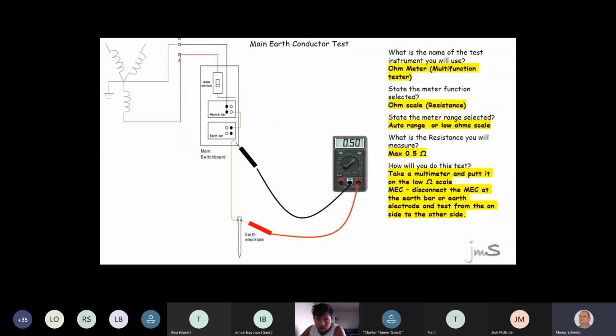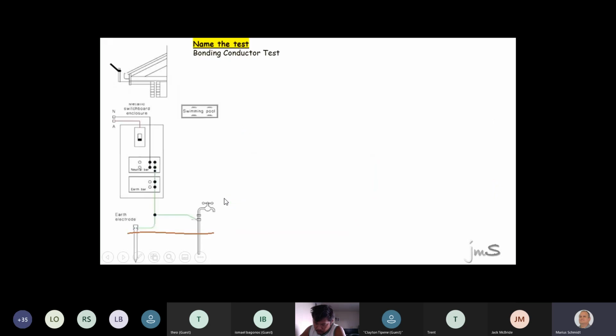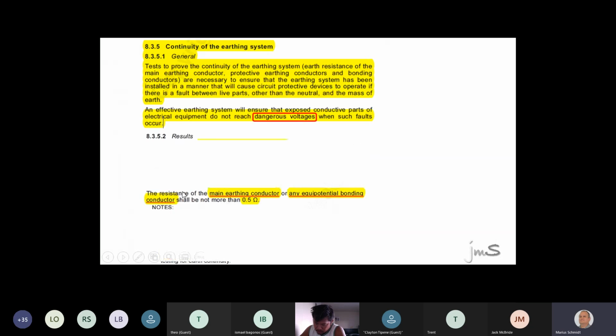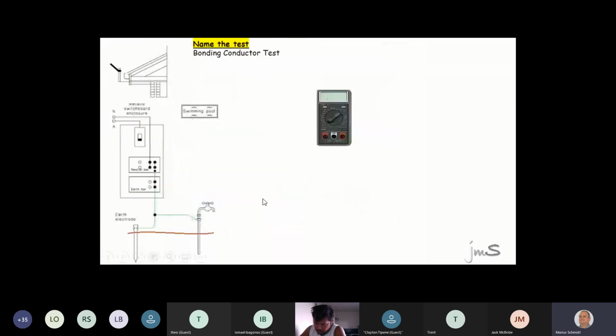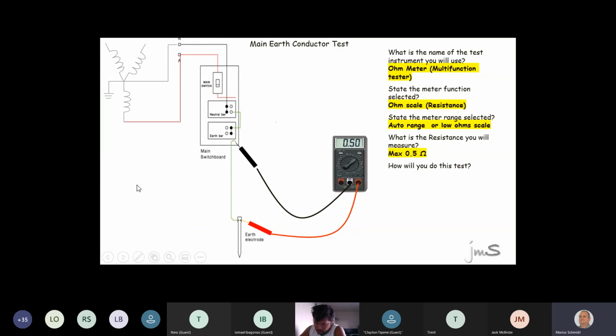But last but not least, is it important to disconnect that wire from there? Why do you guys think so? A, because otherwise I can't get a good connection. B, otherwise I can have a loop via the system and back. You'll be measuring the neutral. You're actually measuring the soil neutral in parallel back. You see that? Right, we will not touch the MEN link because we're only checking the main earth wire. Let me just do this quick. What does it say there? The resistance of the main earth conductor. See that? Right, so we're measuring the resistance of the main earth conductor. So guys, this loop from the back will give you a false reading.